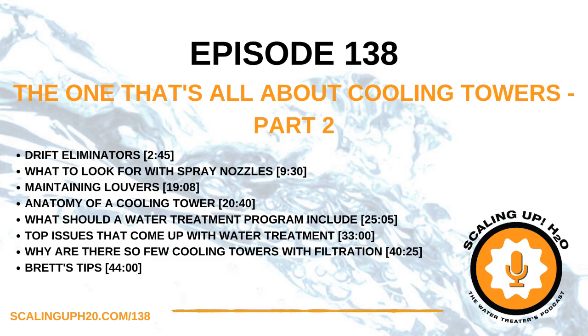Yeah, and the one I would point out is we have chloride ranges on there, or the upper limits of chlorides, but that is highly dependent on temperature. Say you have a stainless steel open cooling tower, you can maybe push the chlorides up to 500 when it's seeing 85 degree water. But you put that in an industrial process and now it's seeing 110 degree water, I'm not recommending pushing the chlorides as high. And there's definitely a chart, I can picture it now, of the chloride limits based on the cooling water temperature. That's a good thing to reference. Do the recommendations change dramatically from manufacturer to manufacturer?